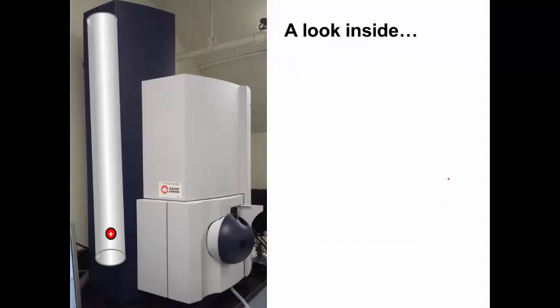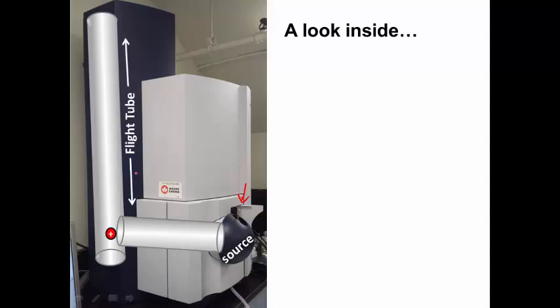So look more closely at how this instrument works. If we were to take that blue cover off, the inside of the mass spectrometer has this really large hollow metal tube. And then leading to that tube, we have another channel. The sample will be introduced at this point right over here. So this is the source region, and it works its way to the back end. That long tube is what we call a flight tube. So a time of flight mass spectrometer, which you'll probably figure out right away how this thing even works. The channel leading into that is simply an ion guide because our compounds that are here have to work their way all the way to the back end, and we don't want them to scatter out and disappear. So that keeps the ions focused.